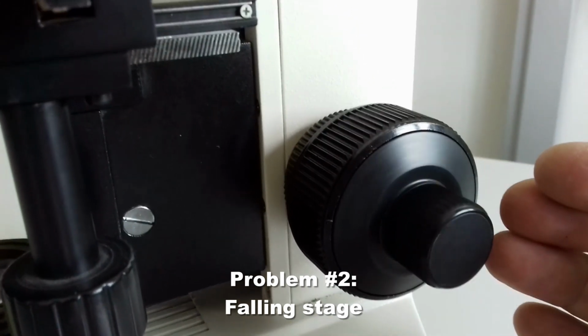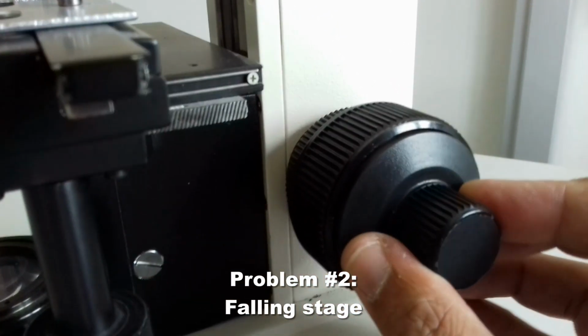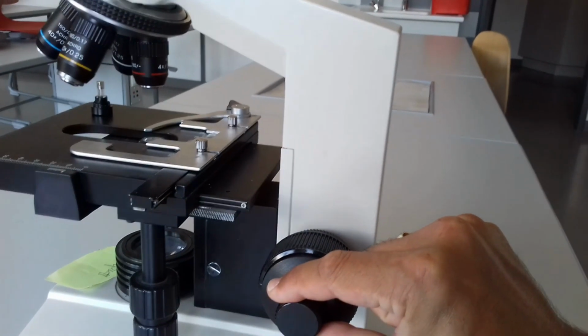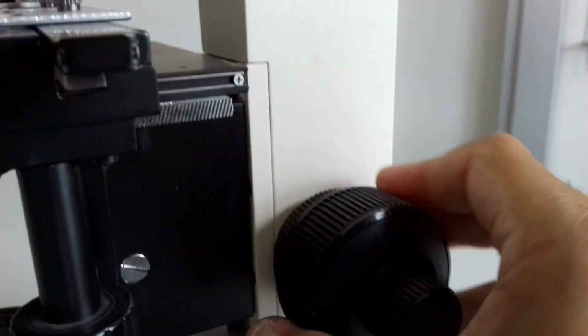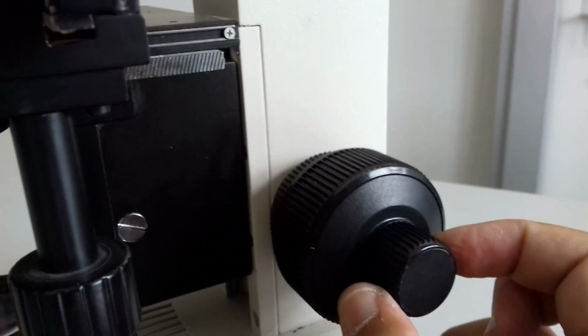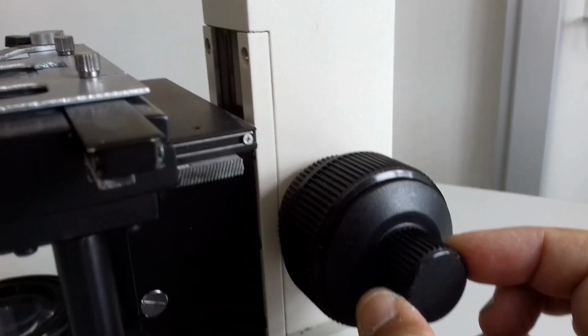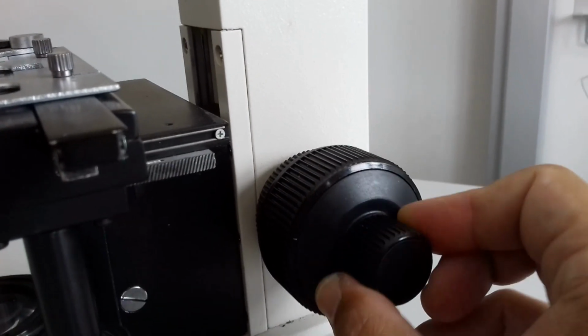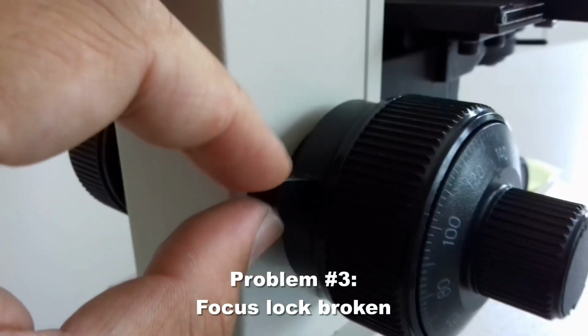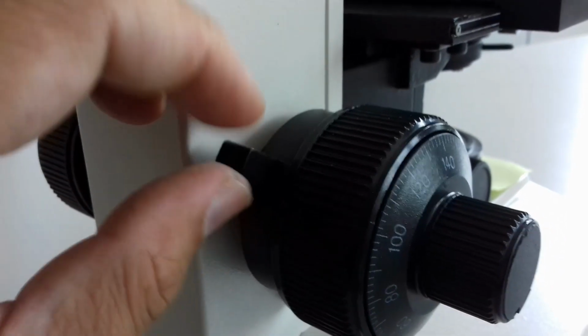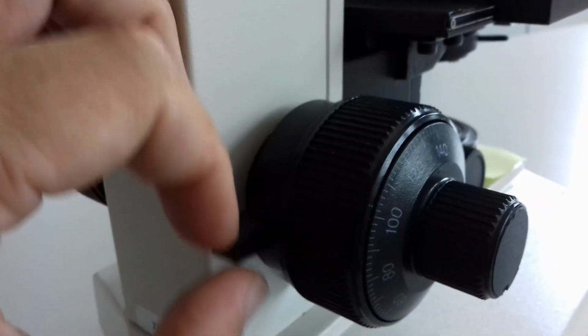So, second problem, a stage. Look at this. This was actually pretty fun. The stage kind of fell. You pulled a little bit on the fine focus knob and some gears became detached and this whole stage fell. This means I have to take apart the coarse and fine focus knob to get that fixed. Another mechanical problem is the focus lock lever, which is supposed to remember the place of the highest focus, and this was completely loose. This was again another microscope. It was moving freely, and it was absolutely not possible to lock the focus.